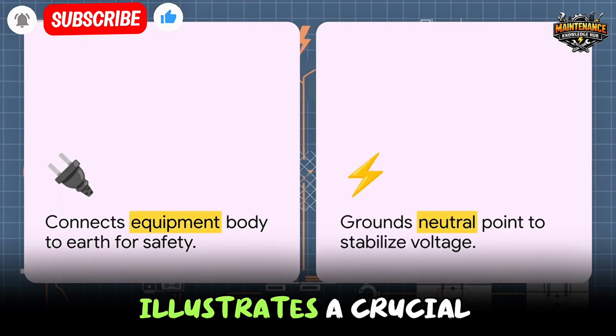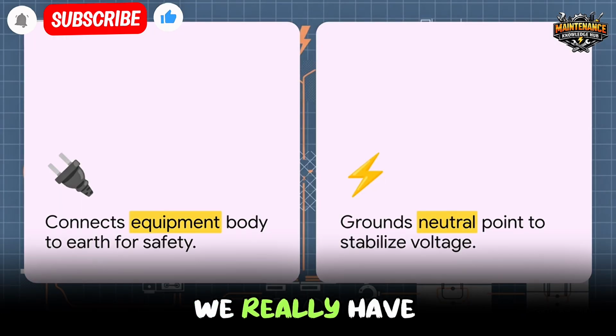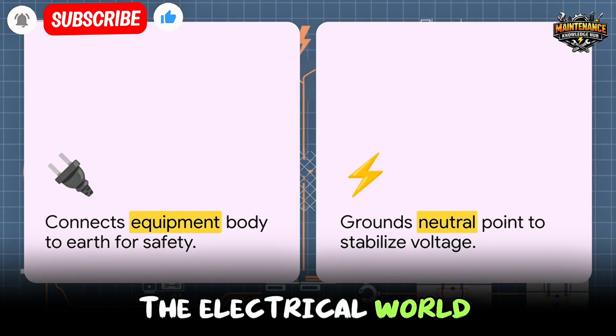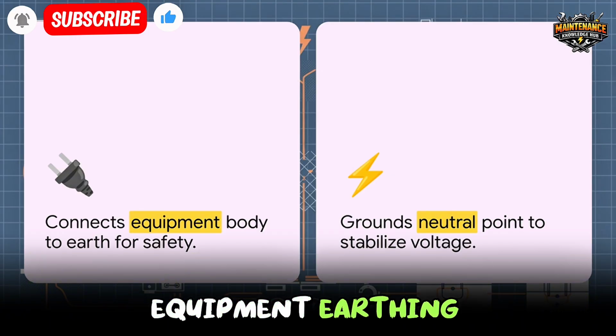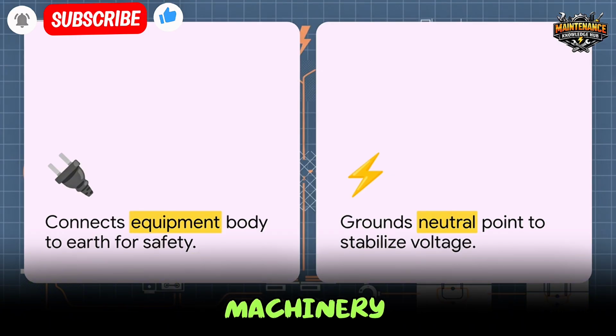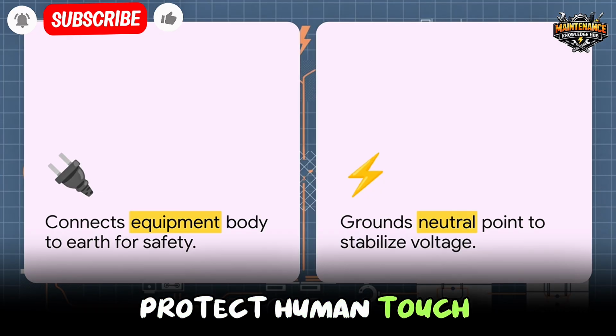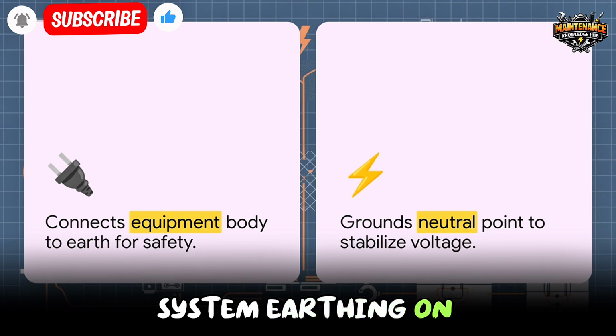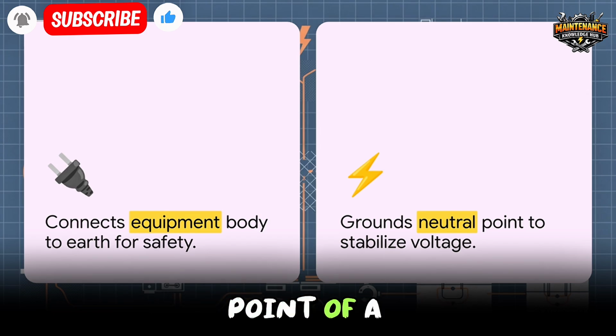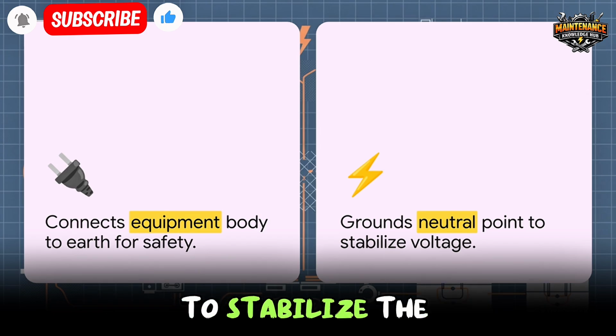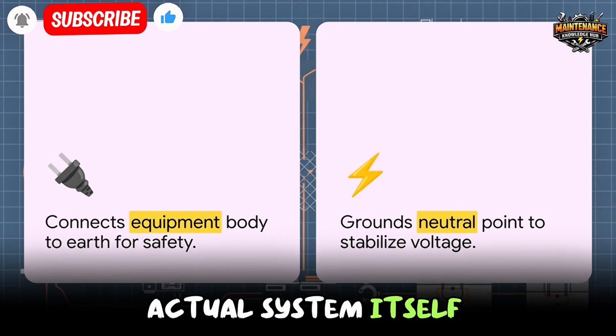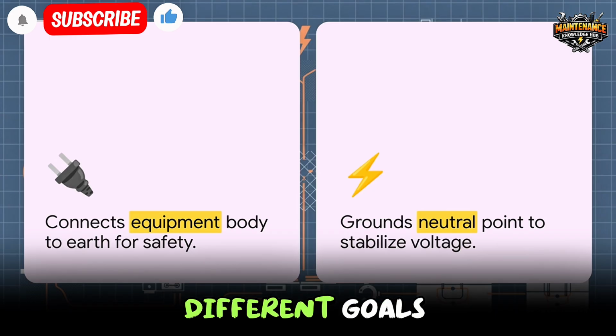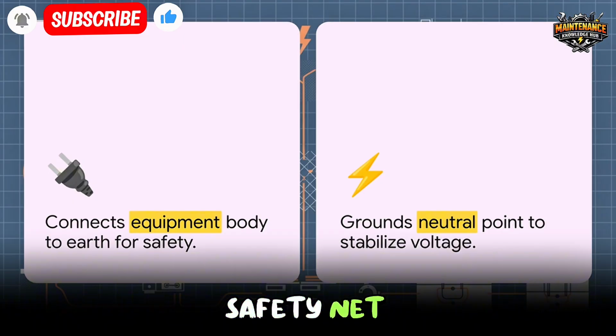And this brilliantly illustrates a crucial distinction we really have to make in the electrical world. See, equipment earthing connects the physical bodies of your machinery, like your panels and motors, to the earth. That's mainly to protect human touch. System earthing, on the flip side, grounds the neutral point of a transformer or generator to stabilize the voltage of the actual system itself. So two very different goals, but one overall safety net.